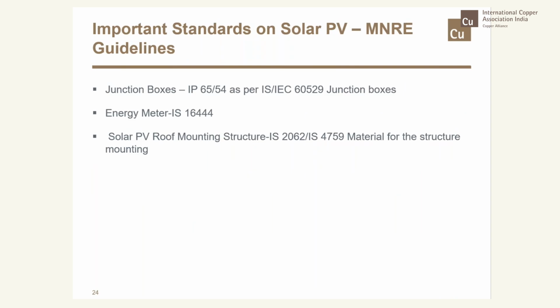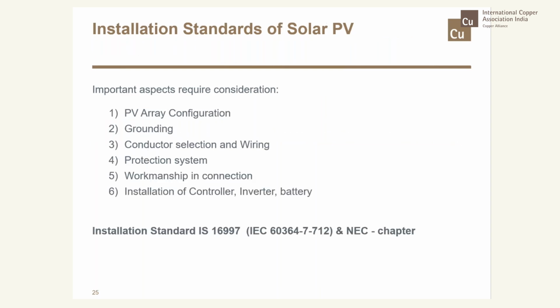An additional requirement of MNRE guidelines is the junction box. This is IP protection. Energy meter, IS 16444. This is again a kind of mandatory requirement. For the solar roof mounting structure, the corresponding standards have been mentioned. Finally, PV installation standards are also very important, as the installation process is a bit complex, involving PV array design. Grounding is very important. Wiring has to be proper, with site selection and insulation type which can sustain high temperature and solar radiation. All these are essential requirements.